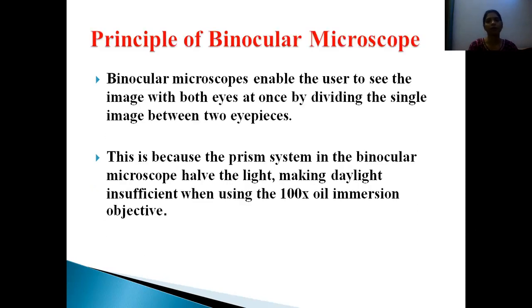The principle of binocular microscope: A binocular microscope enables the user to see the image with both eyes at once by dividing the single image between two eyepieces. The prism system in the binocular microscope halves the light, making daylight insufficient when using the 100x oil immersion objective.